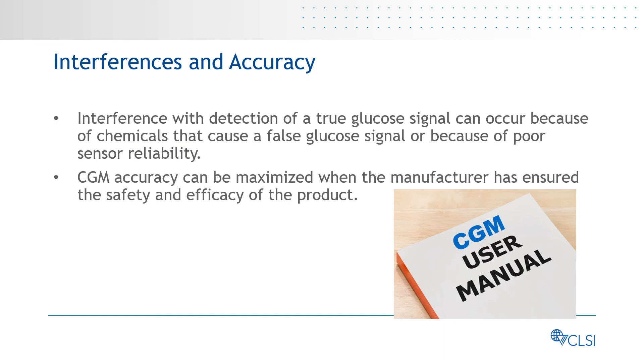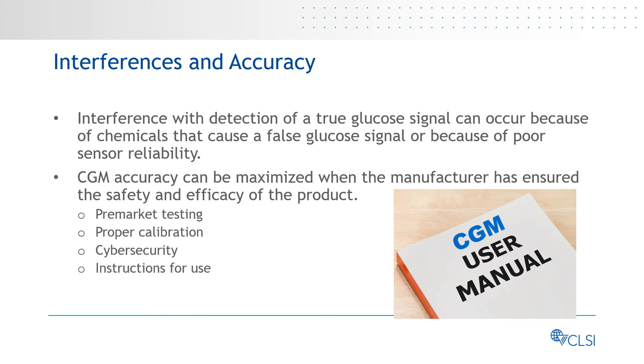CGM accuracy can be maximized when the manufacturer has ensured the safety and efficacy of the product through appropriate pre-market testing, proper calibration of the devices, effective cybersecurity controls, clear instructions for use in the product labeling, and the system is operated properly by the users according to these directions.